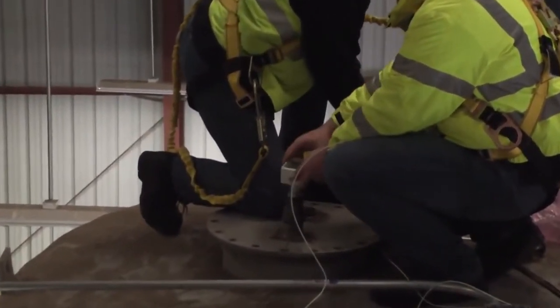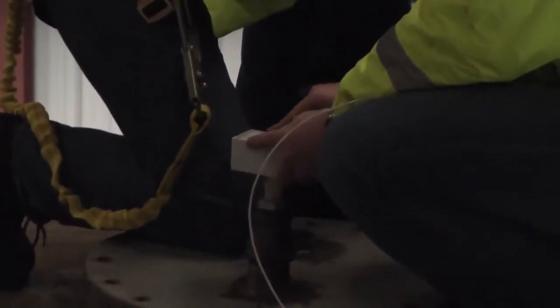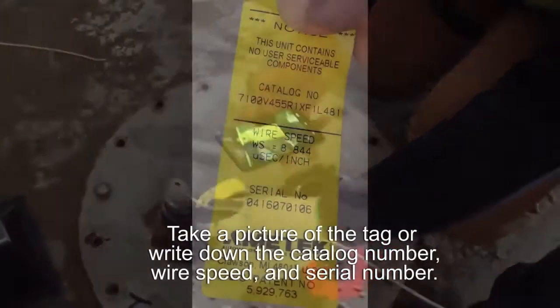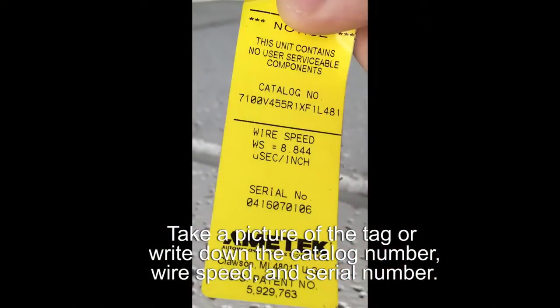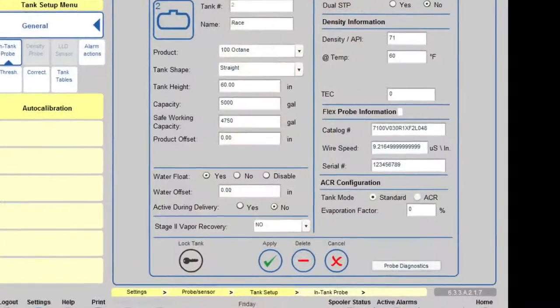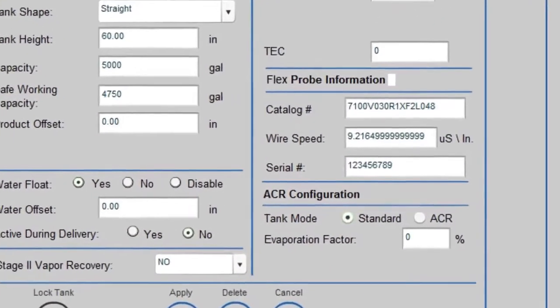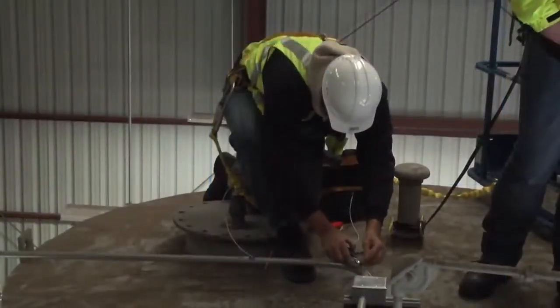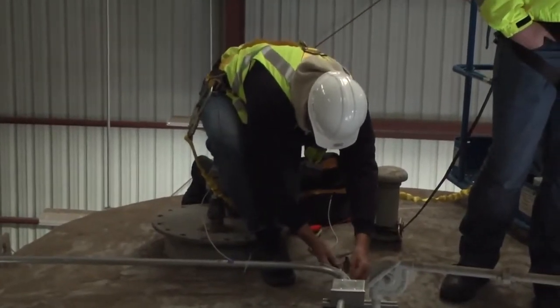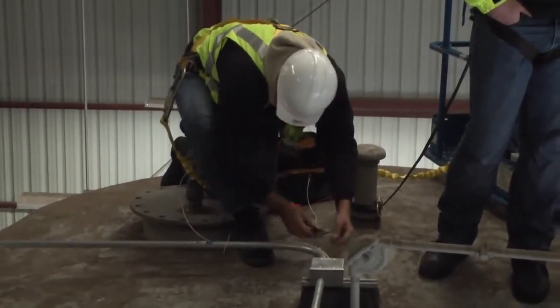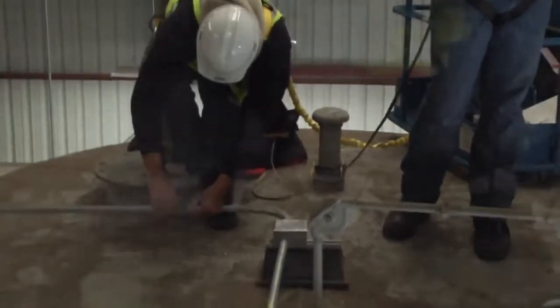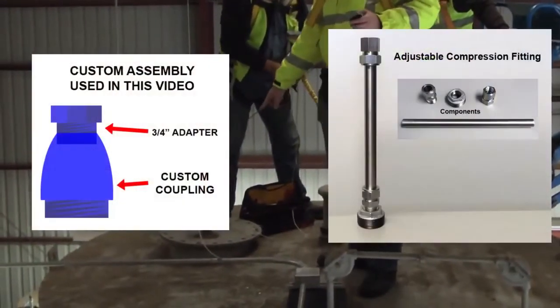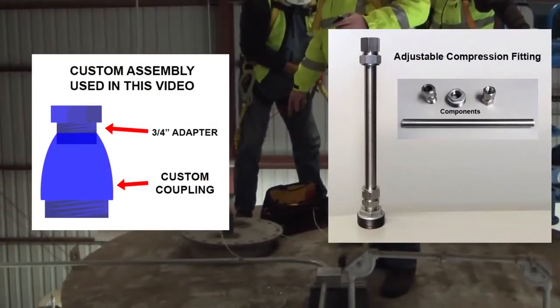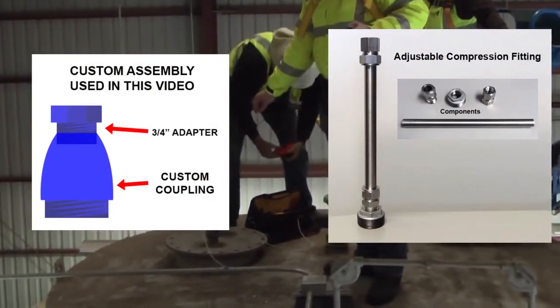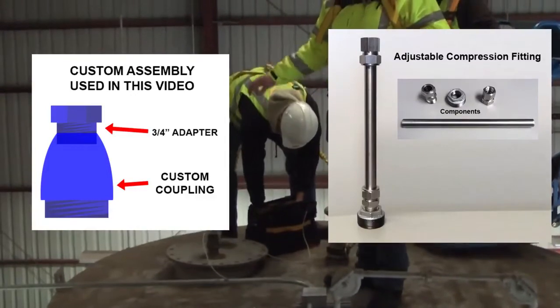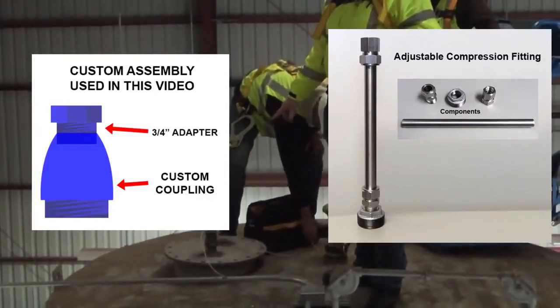Now we're going to thread our junction box on. Take a picture of the tag or write down the catalog number, wire speed, and serial number. This information will be used when setting up the flex probe in the tank gauge. Make sure to dress your cables so they are out of the way and no one will trip over them during maintenance activities. So if this was an adjustable piece like in the manual, you'd want to make sure that the probe is touching the bottom of the tank, and then you would pull it up a couple inches because the probes will actually grow during temperature changes.